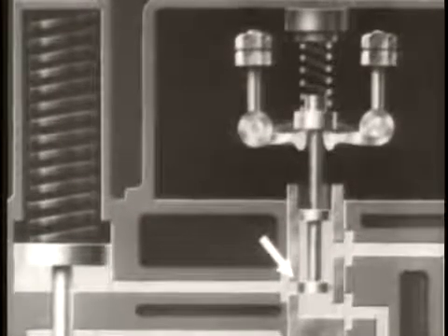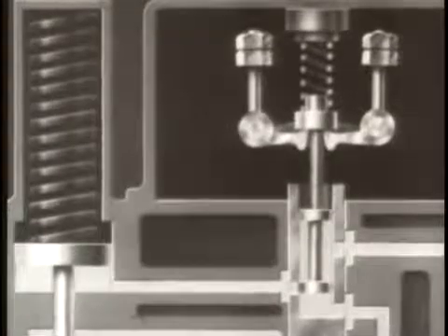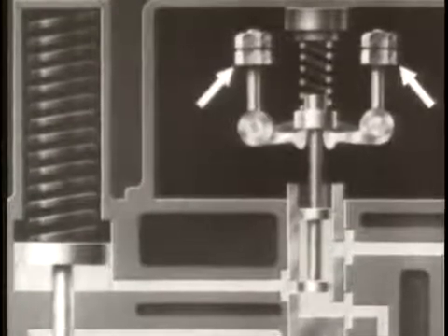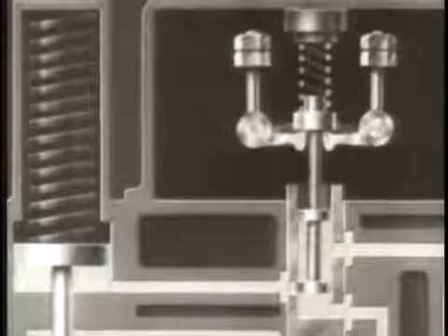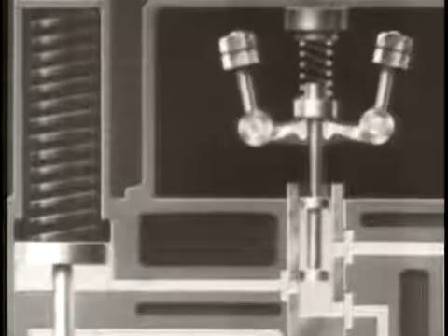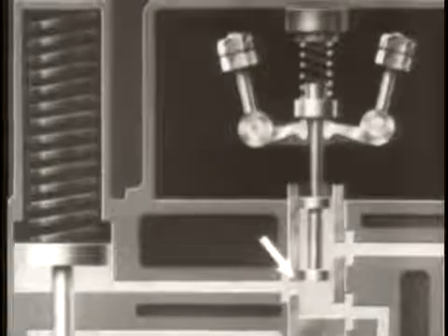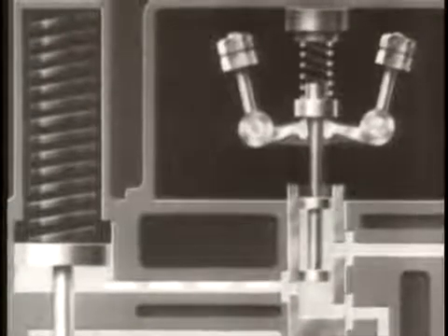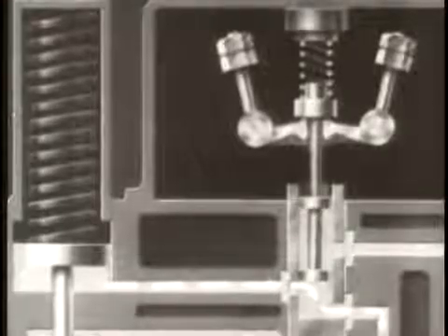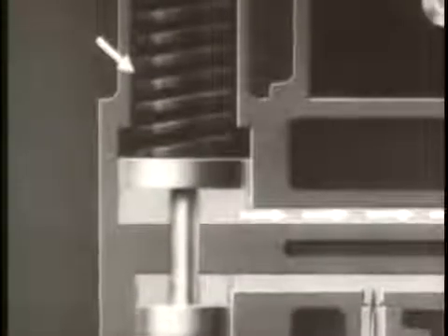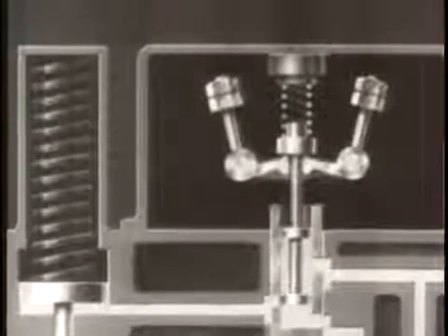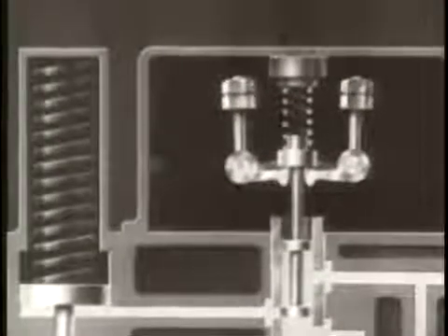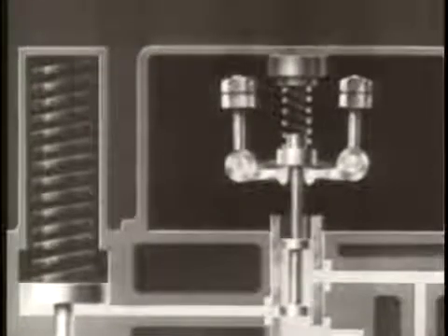When the engine is running at a set speed, the port to the power cylinder is covered by the pilot valve plunger. The plunger is held in this position by the flyweights. If the engine load decreases, however, the engine speeds up, and the additional centrifugal force throws the flyweights outward, raising the pilot valve plunger. This opens the port, and oil from the power cylinder is now allowed to flow through the pilot valve cylinder into a drainage passage to the oil sump. The power spring forces the piston down, actuating the linkage to the fuel system controls, and the supply of fuel to the engine cylinders is diminished. As the engine speed returns to the set rate, the flyweights resume their original position, and the pilot valve plunger again covers the port.